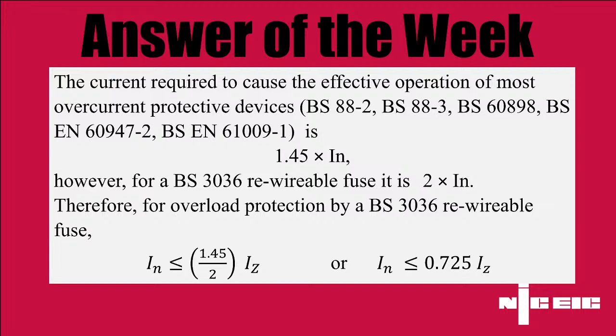But a BS 3036 fuse, a rewirable fuse, is slightly different in that it's 2 times In. So you've got that extra factor in, and if you look at 1.45 divided by 2, that's where we get our value of 0.725. And you notice that information's actually in BS 7671, isn't it, Dan, in the appendix?